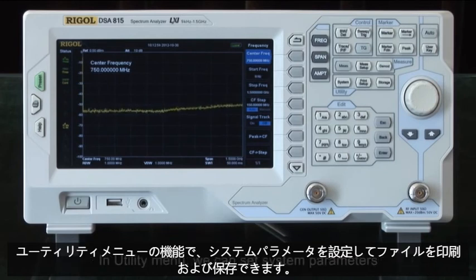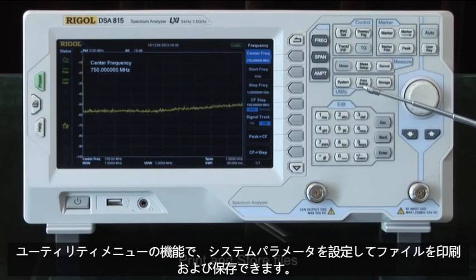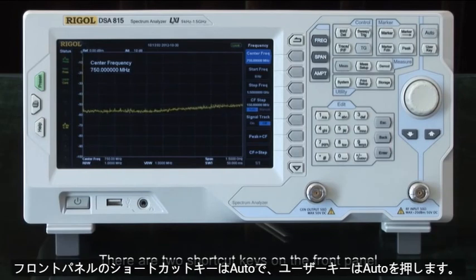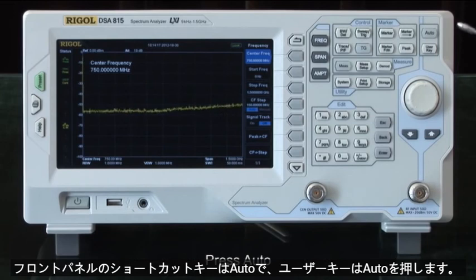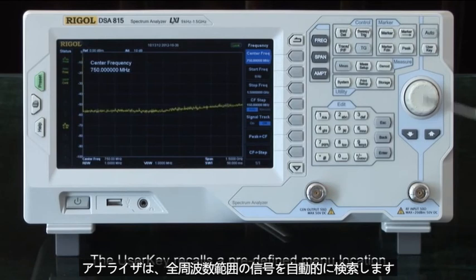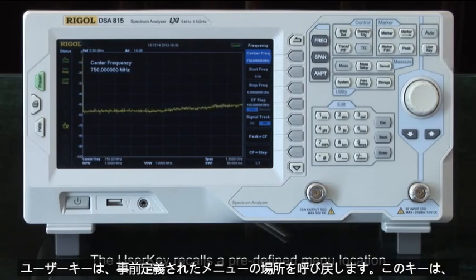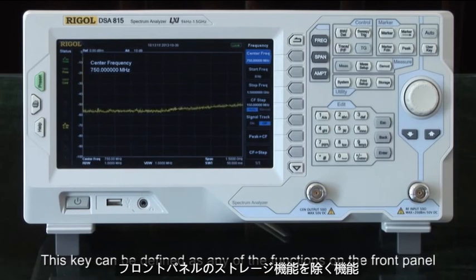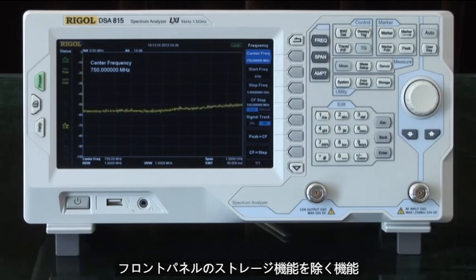In the utility menu we can set system parameters, print, and store files. There are two shortcut keys on the front panel: auto and user key. Pressing auto, the analyzer will search for signals in the full frequency range automatically. The user key will recall a predefined menu location and can be defined as any of the functions on the front panel except the storage function.